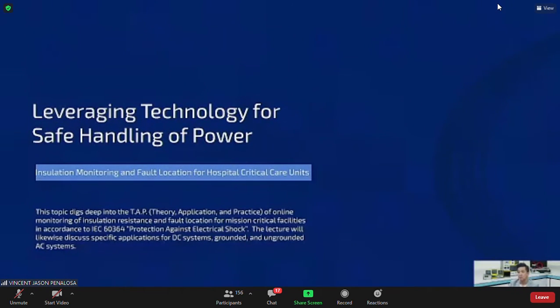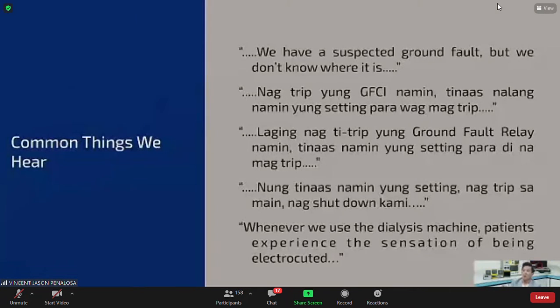We're going to be talking about leveraging technology for safe handling of power. It's basically understanding insulation monitoring and fault location for hospital critical care units. This presentation will dig deep into the theory, application, and practice of online monitoring of insulation resistance and fault location for mission critical facilities in accordance with IEC 60364. Basically, IEC 60364 is a standard for protection against electrical shock. This lecture will likewise discuss specific applications for DC systems, and grounded and ungrounded AC systems, if we still have time. Now, to start off, these are the common things we hear.